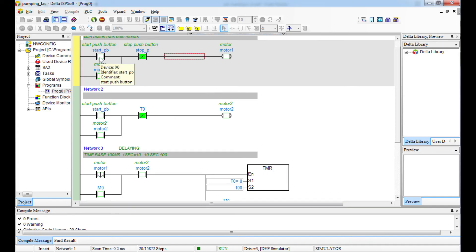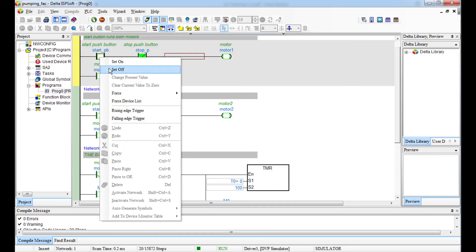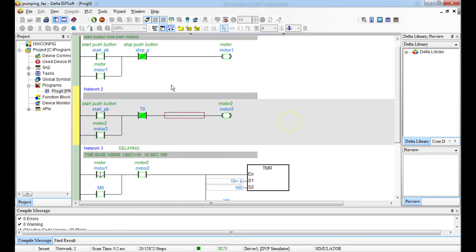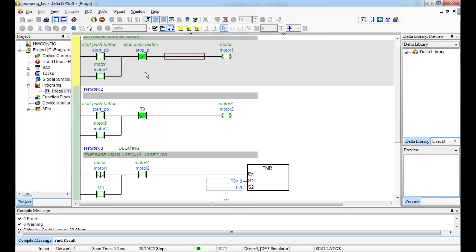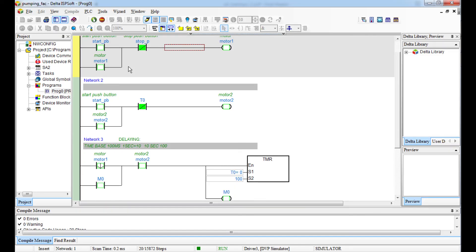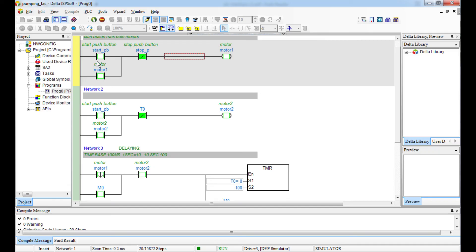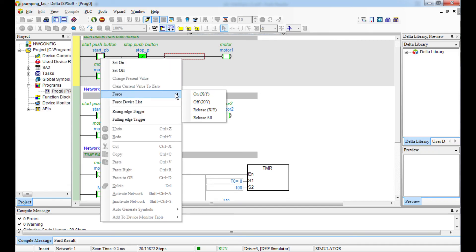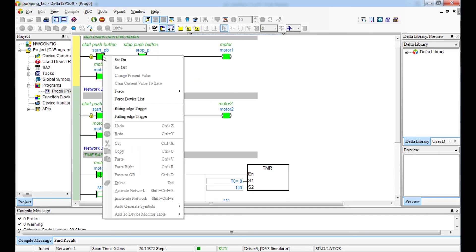Something to be careful about when simulating: a push button must be forced on and then forced off. If you force it on and leave it on, it will interfere with your program because you're not simulating what happens in real life where a push button closes momentarily and returns to its initial position.